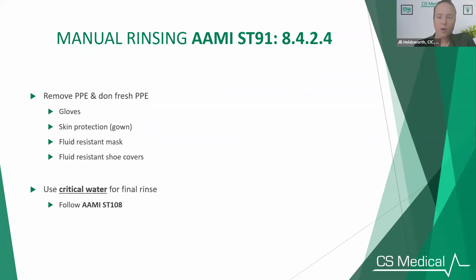So let's talk about rinsing for a moment. If you are manually cleaning, then you have to manually rinse. Again, the IFUs will state how many times you have to manually rinse and for how long. A lot of times I'll see manually rinse for 2 minutes after your cleaning. The hard part is you can't just manually rinse in the same sink you just cleaned in. So you're going to have to drain the water and make sure that the sink is disinfected, to make it a safe process. If you have two sinks, like in an endoscopy area, where we have a double sink, you can rinse in that second sink.